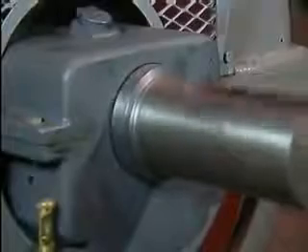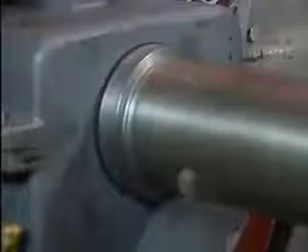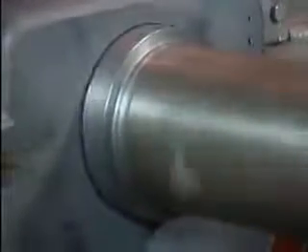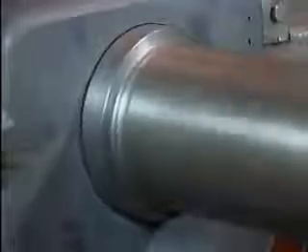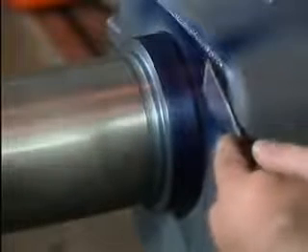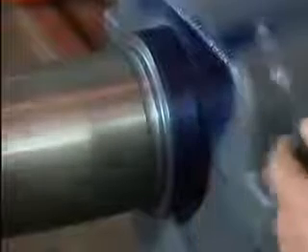Then the motor can be started up. As the motor comes up to speed, there's a noticeable amount of axial shaft movement until the magnetic field pulls the shaft into its normal operating position. At that point, the shaft is sprayed with layout dye, and a line is lightly scribed into the dye using the end bell of the motor as a reference point.